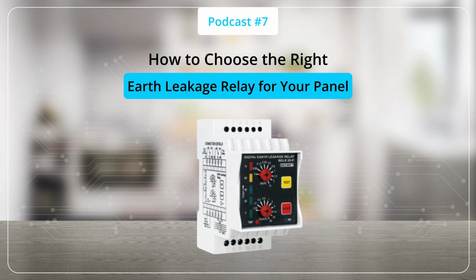Improper wiring is another issue. Running the earth conductor through the CBCT can make leakage detection inaccurate and reduce system reliability. In TNC systems, using earth leakage relays without proper protective earth-neutral separation can increase leakage-related issues. Regular testing and inspection of protection devices are equally important. Without routine verification, hidden faults may go unnoticed until a real failure occurs. By avoiding these common mistakes, you can ensure that the protection system performs exactly as intended whenever a fault occurs.